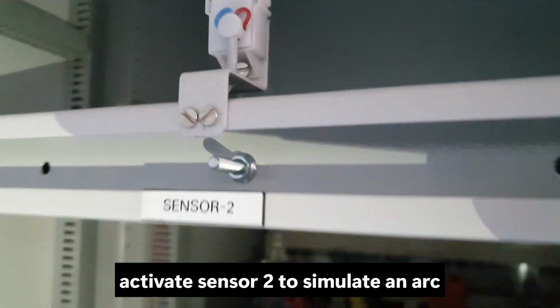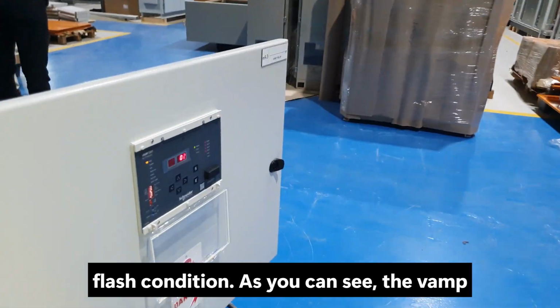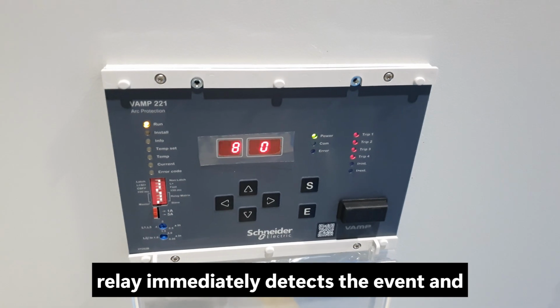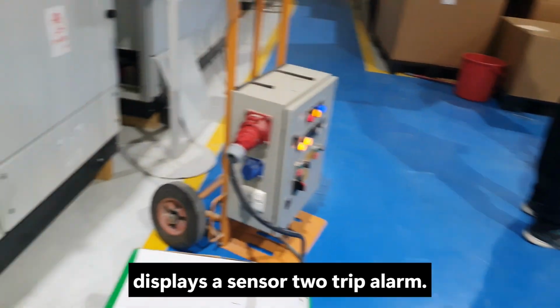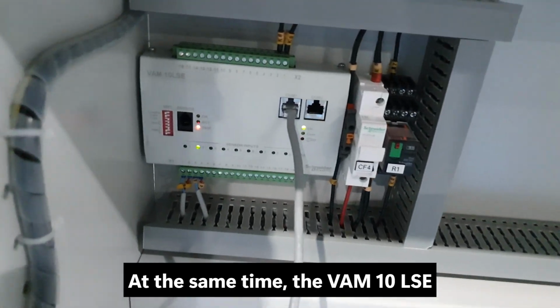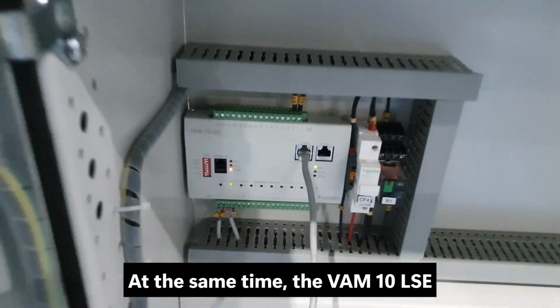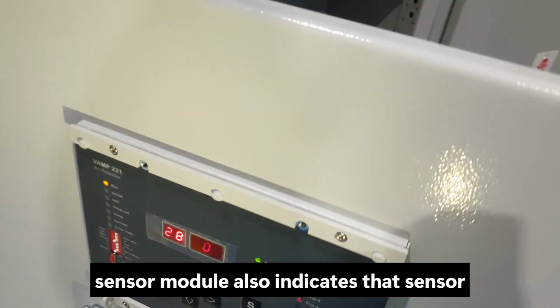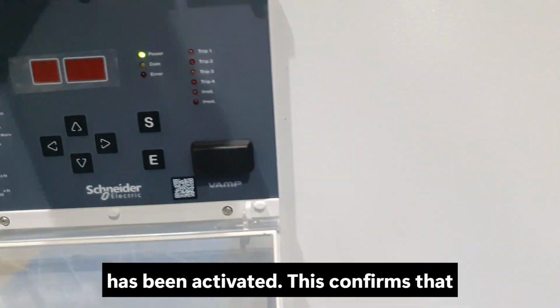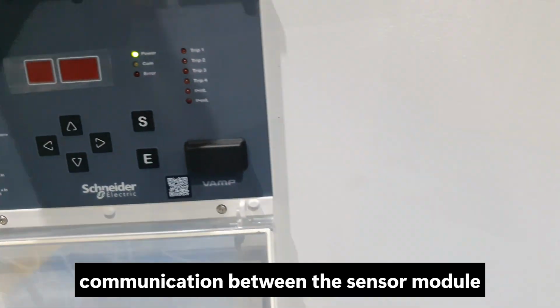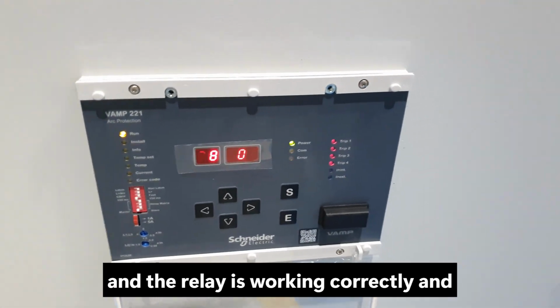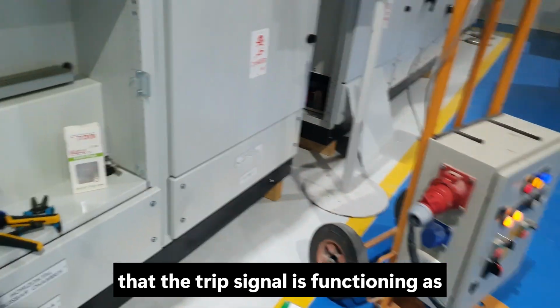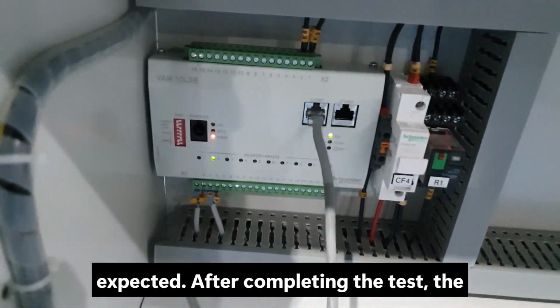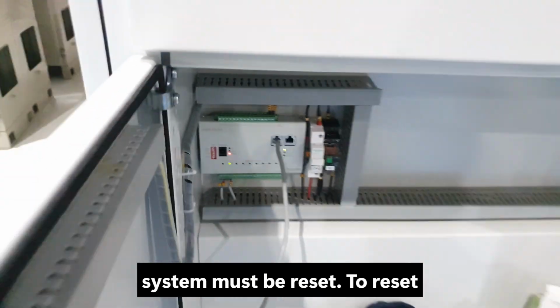I will activate Sensor 2 to simulate an arc flash condition. As you can see, the VAMP relay immediately detects the event and displays a Sensor 2 trip alarm. At the same time, the VAM 10 LSE sensor module also indicates that Sensor 2 has been activated. This confirms that communication between the sensor module and the relay is working correctly, and that the trip signal is functioning as expected. After completing the test, the system must be reset.